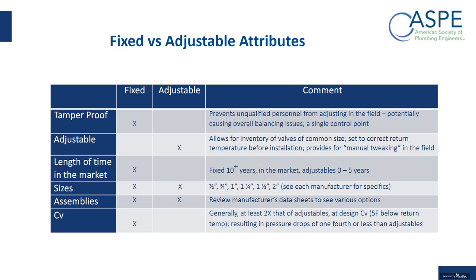With the adjustable, obviously they are adjustable. There are knobs on there that can be turned. They do have some type of locking mechanism on them, but they can be relatively easily overridden. But the nice thing about the adjustables, especially with contractors and wholesalers, is that now they don't have to order valves of all different temperatures and inventory all these different temperatures. They can order one size valve, 1/2 inch, 3/4 inch, and when a call comes for these valves, the contractor can set them for whatever return temperature they need for that application. So it also allows for manual tweaking in the field. If something isn't exactly right, you can adjust it a little bit to bring it in to a tighter tolerance if that's critical to you in the application.